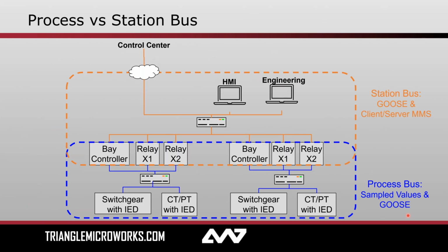So lastly, before I turn it back over to Matt for one final demo, I want to talk about two terms, process bus and station bus. These are not terms that actually appear in the 61850 standard. You can download all the different documents from the IEC and you won't see these. However, they are quite pervasive in the industry. If you're attending conferences or reading papers or trade magazines, you're certainly likely to see process bus and station bus. So I just want to quickly define what they mean.